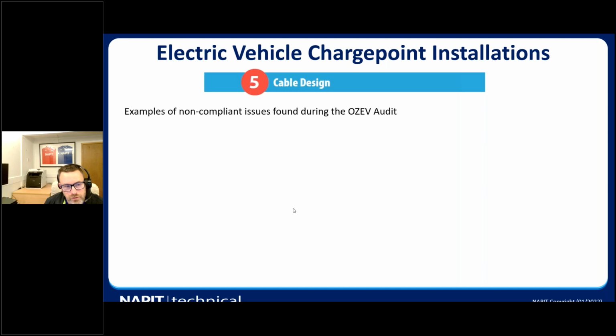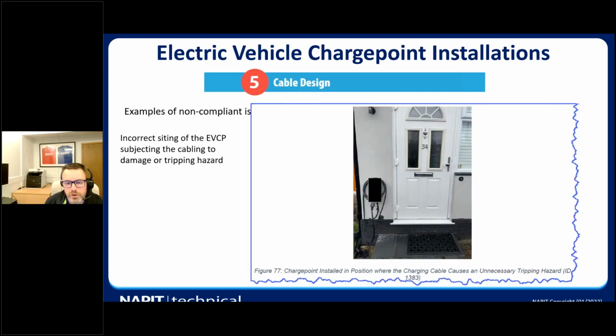And these are examples of non-compliant issues found during the audit. So we're looking at the incorrect siting of EV charge points, subjecting the cables to tripping and hazards to people using them. So there's a cable here, obviously, that will come out the door, can't quite see it, but the cable went underneath the doorstep, in front of the doorstep, so people can't be tripping up on this, causing hazards. So we've got to be mindful of that.